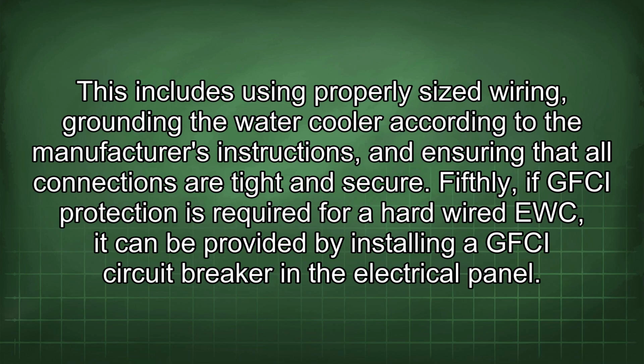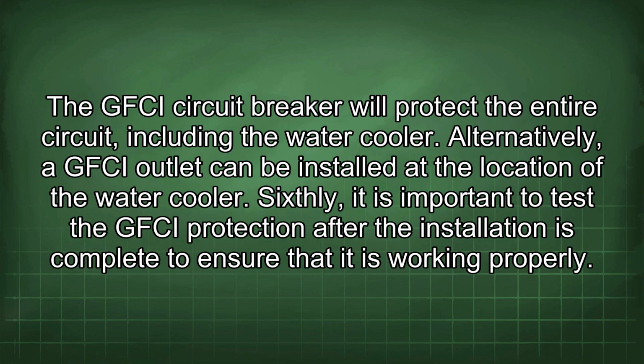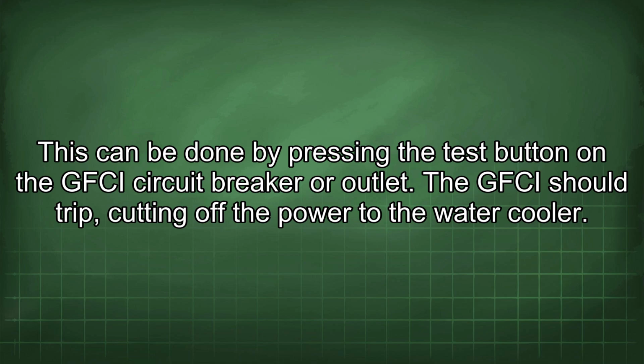Fifthly, if GFCI protection is required for a hardwired EWC, it can be provided by installing a GFCI circuit breaker in the electrical panel. The GFCI circuit breaker will protect the entire circuit, including the water cooler. Alternatively, a GFCI outlet can be installed at the location of the water cooler. Sixthly, it is important to test the GFCI protection after the installation is complete to ensure that it is working properly. This can be done by pressing the test button on the GFCI circuit breaker or outlet. The GFCI should trip, cutting off the power to the water cooler.